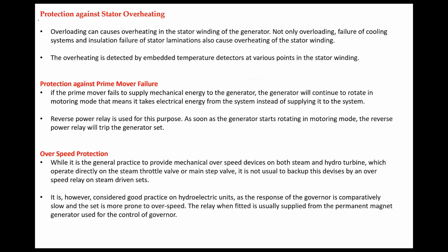Next, protection against stator overheating. If the stator is getting overheated, what happens? Overheating happens mainly because of loading the generator more than its capacity, or if the cooling mechanism fails. Definitely in big alternators, there will be oil circulation and air circulation. For oil circulation, a pump called the lubricating oil pump will be continuously running. For air circulation, fans will be continuously running to cool the alternator. If that oil circulation or air circulation stops, what happens?